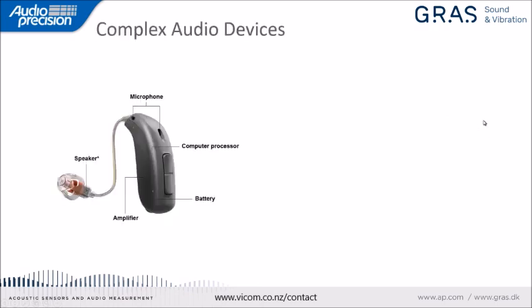A little bit about hearing aids — these are marvelous little devices from an audio test perspective. They have both acoustic input and acoustic output, which is unique from an audio test point of view, but they're also quite complex devices. They typically have one or more microphones, a power amplifier, a loudspeaker called a receiver in the hearing aid industry, a computer processor for digital signal processing, and they are battery powered with some controls, all in a tiny package.